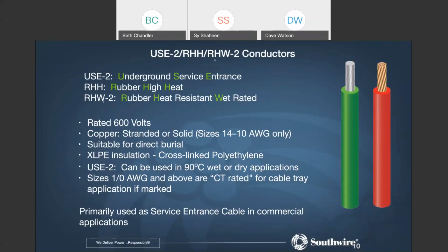And so I want to be sure and point out something here about this particular product. We make products that are listed as USE-2 only, without the RHH and RHW designations. Those products are part of what we would typically call UD or URD, so underground residential distribution. These may be the conductors that go to your home, as a matter of fact, if you have underground power service to your home. And the ones that are rated USE only are not allowed to be used inside of a building. They can only be used outdoors. They do not have the proper flame retardancy for indoor use.